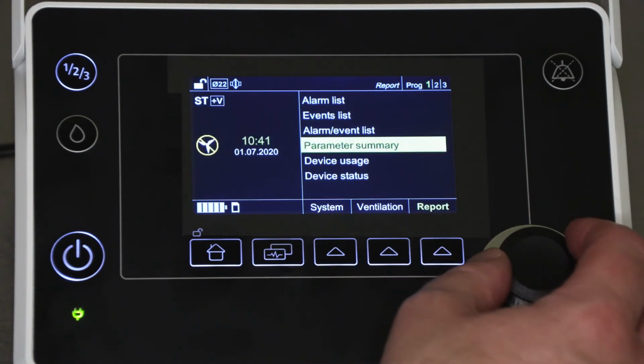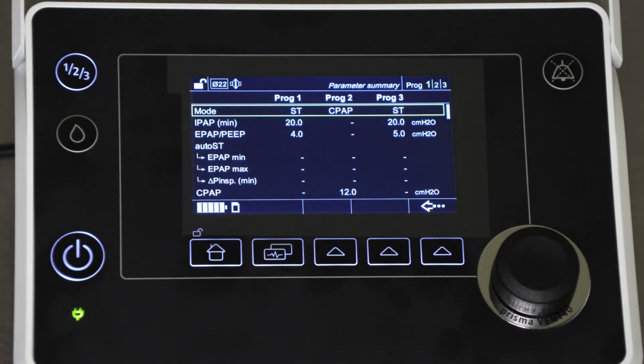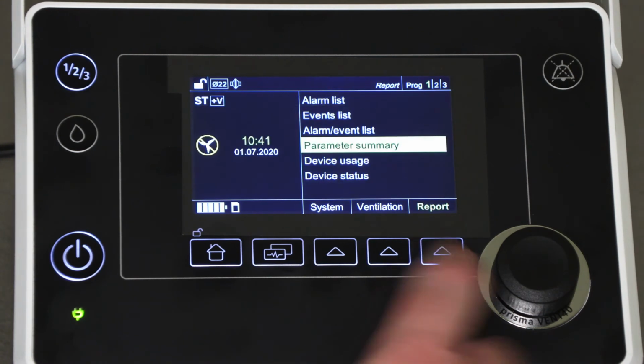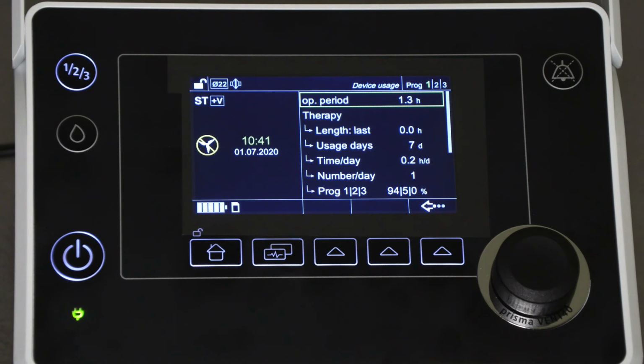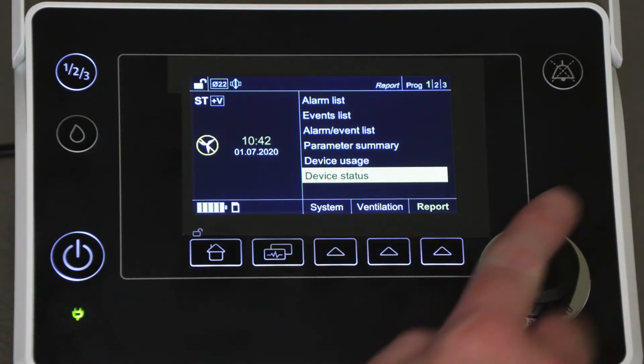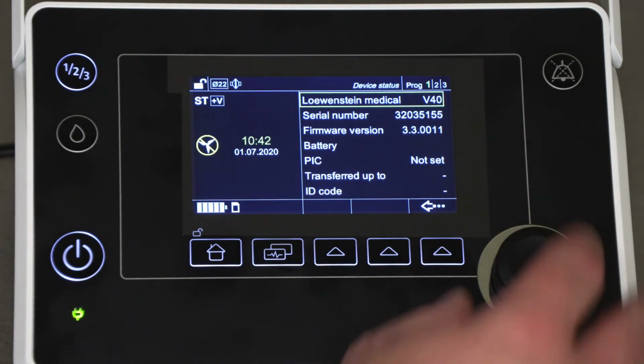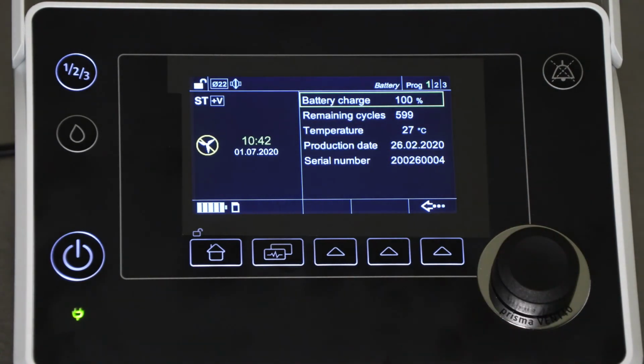The parameter summary shows all the available ventilation programs and the therapy settings applied to each. Device usage statistics gives on-screen information relating to how much the ventilator has been used. And the device status gives the firmware and battery charge information. This information list is also available in the system menu.